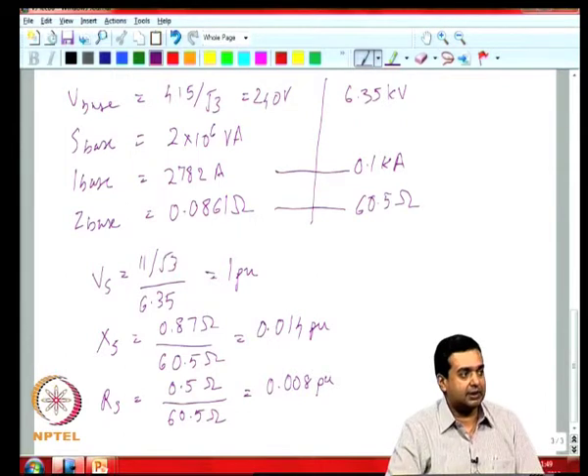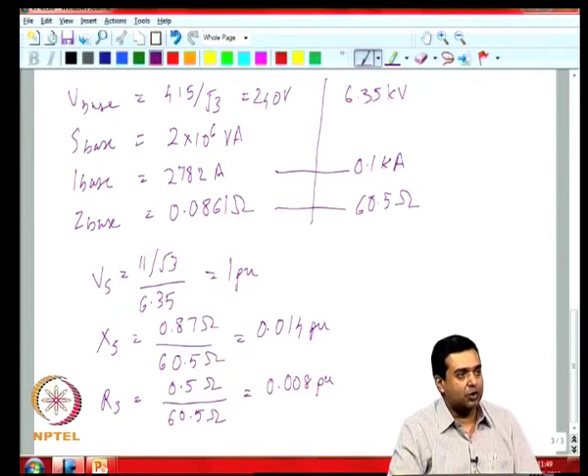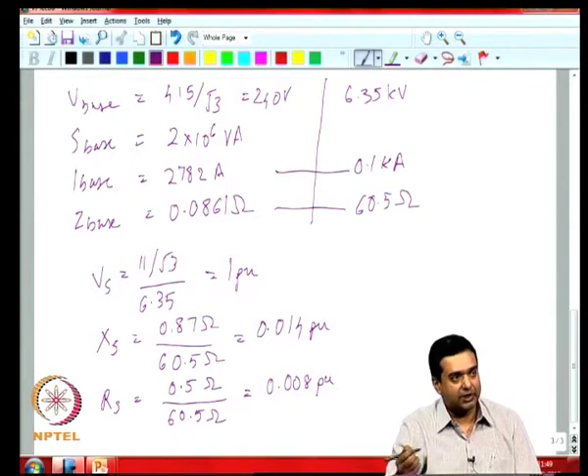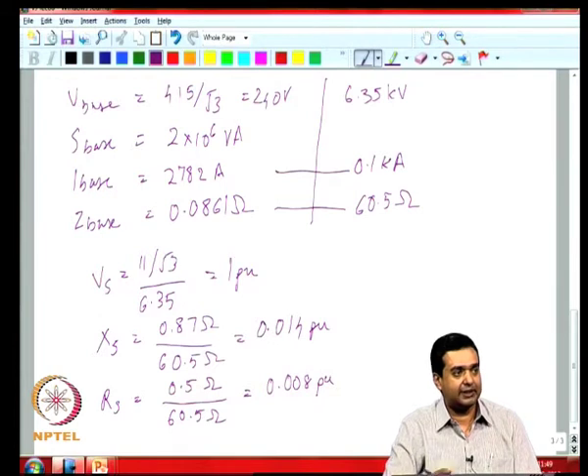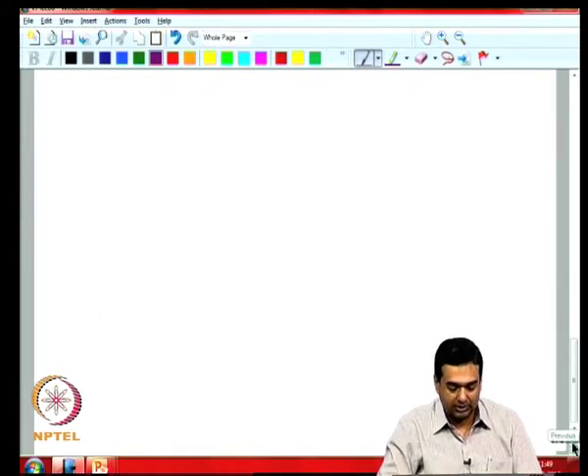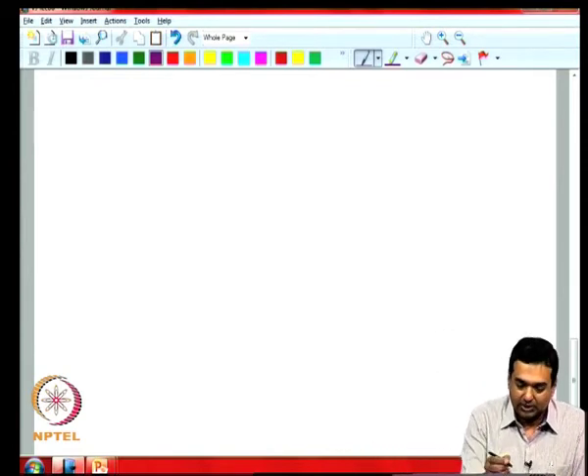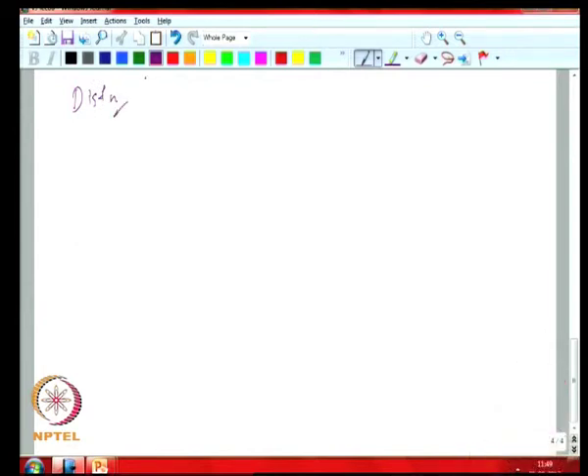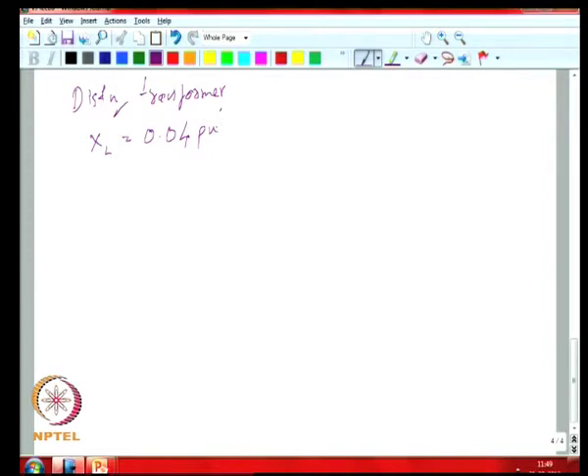Comparing with numbers from the last class, your X_S and R_S — as seen at the reduced power level of the distribution transformer compared to substation power level — the per-unit quantities are actually lower now because you have changed to a lower power base. For the distribution transformer itself, your X_L and R_L stay the same because you are using the transformer values as the base quantities.